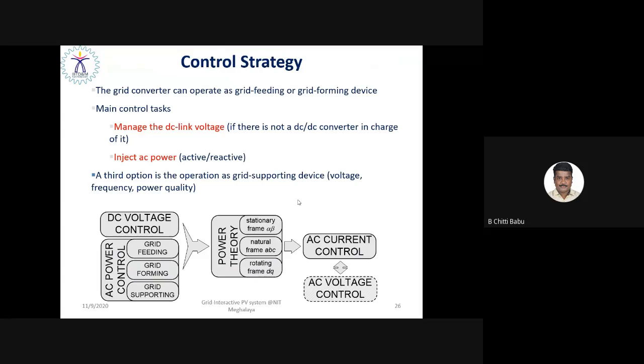Yes, so now the control strategy. As the grid interactive power converter, it has to handle both the DC as well as the AC parameter. The DC parameter is an input parameter that is derived from the DC to DC boost converter in terms of DC link voltage, and the output parameter is basically an AC parameter. Basically, it involves the grid parameters, which are voltage as well as frequency.